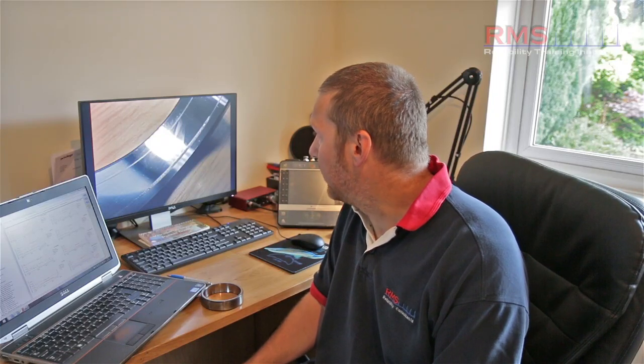And I think the root cause of this is overloading of the lock nut and sleeve. So basically it's been preloaded but overloaded the bearing, which has caused the damage. So that's it really. The bearing's back in service, the new one, everything's looking fine, so we'll continue to monitor that, and hopefully it'll be a number of years before we see another defect. So thank you.